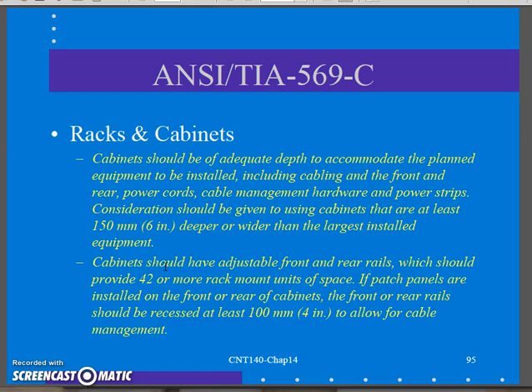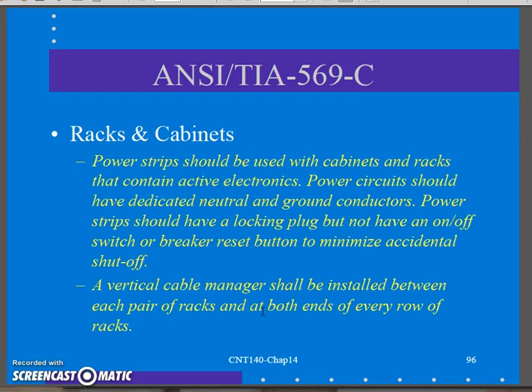Cabinets should have adjustable front and rear rails and should provide 42 or more rack-mount spaces. They also discuss cable management here, giving you dimensions and guidelines so you don't have to guess. Power strips should be used with cabinets and racks containing active electronics — they have all kinds of rack-mount power strips that mount horizontally or vertically, some with meters showing you, for example, if you have a 20-amp circuit you're using 12 amps so you know you're not going to blow a breaker. Vertical cable management should also be used — at a bare minimum — in your racks or cabinets.